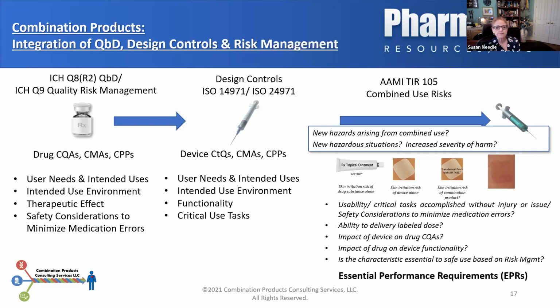So consider this possibility. I have a drug that has excipients, and maybe I'm using that drug in an implantable pump. One consideration might be that the excipients from my drug formulation interact with the tubing of my pump mechanism, and the tubing then releases oxidants that cause my pump to fail. Maybe it causes it to rust, so that it seizes up and the motor no longer functions. That leads to lack of medication, which is a source of harm. Therefore, in that case, I'm looking at an impact of the drug on the medical device functionality.